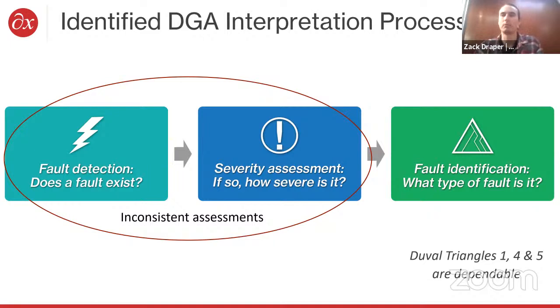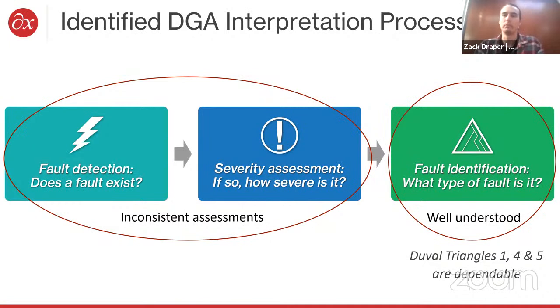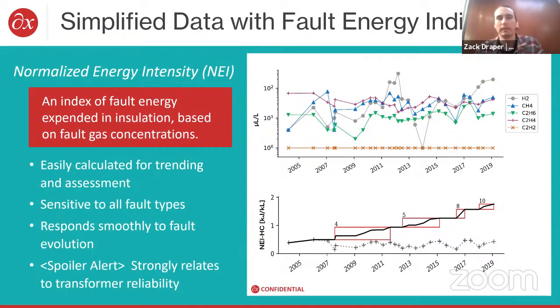Fault identification is fairly reliable. If you use Duval triangles, they're pretty dependable, as long as you're using incremental gas values on clearly identifiable faults and not just on noise values. So what we really wanted to focus on was this risk assessment in reliability-based DGA. One of the first things we did was to try to simplify the problem. The gases are not what is going to cause the transformer to fail. It's the fault which is generating the gases that is going to cause the transformer to fail. Whether it's a weak spot in the transformer windings, burning paper, or a loose tap connection, those kinds of things are what's going to fail the transformer, and the gases are just a symptom of the problem.